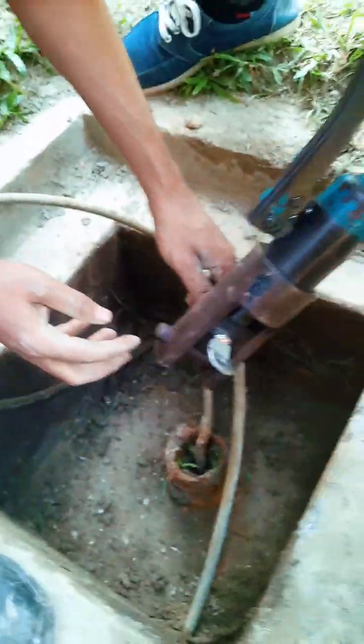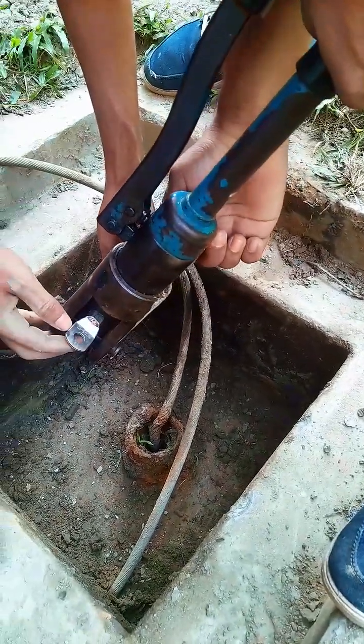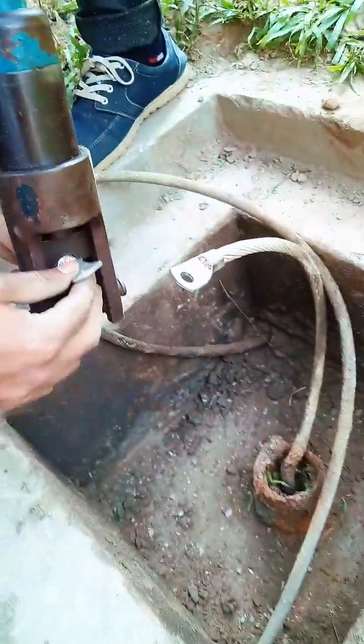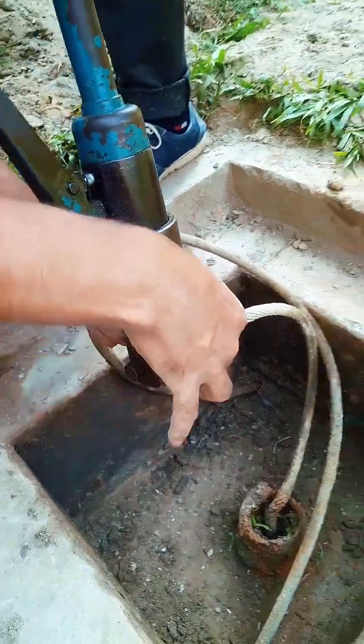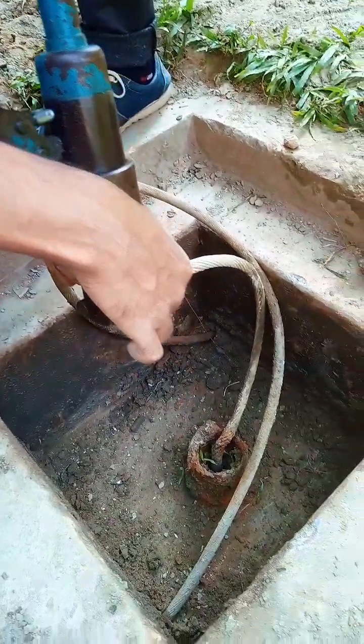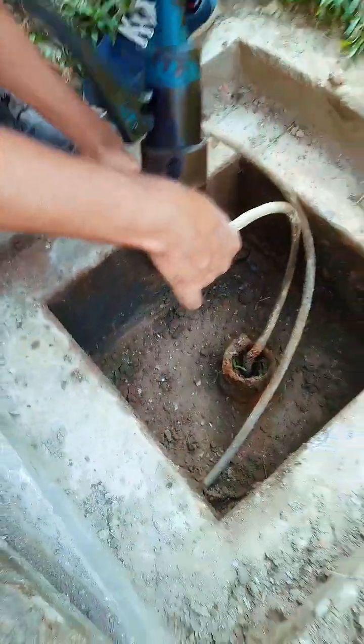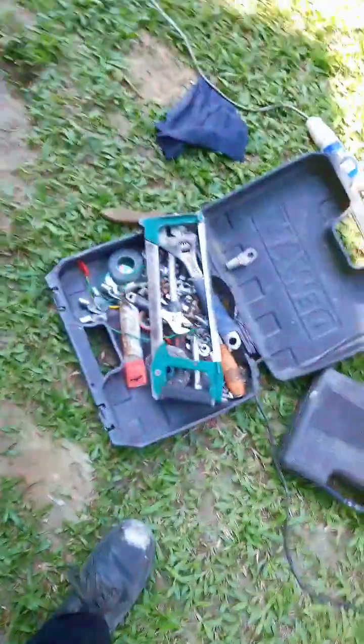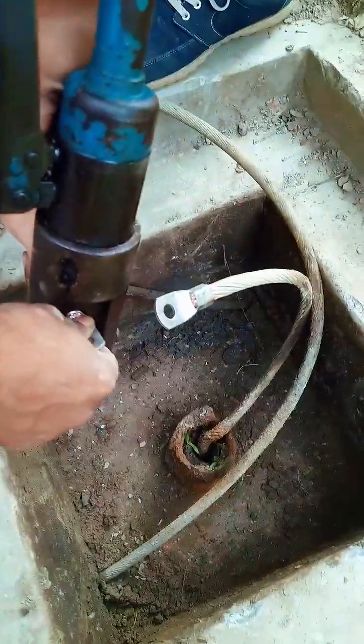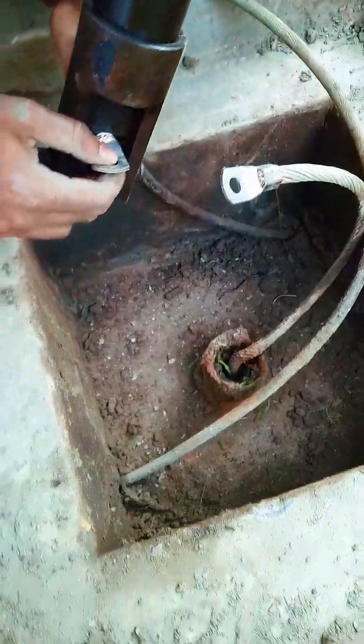Cutting and surface preparation. Using a grinding machine, we cut the corroded portion. Then we manually cleaned the copper surface, sanding, brushing, and polishing until the conductor became shiny and bright. This step is extremely important. Lightning discharge and fault current require a clean metallic contact area. Any oxidation layer introduces resistance and heat.